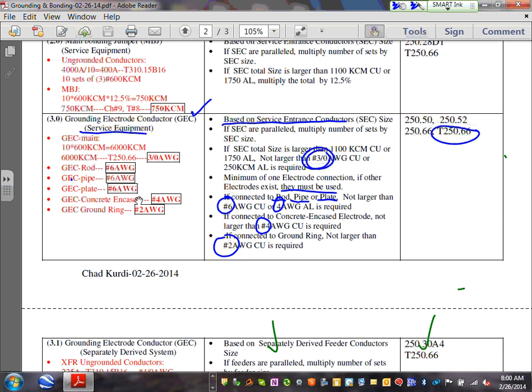When you have a grounding electrode conductor, you tie it to that copper plate, and then from that copper plate, you can go to a ring. Here's a rod. If you go to a rod, you don't have to go more than number 6 AWG. If you tie to concrete encased electrodes, a foundation, you don't have to go larger than number 4. If you tie it to a ring, a ground ring around the building, you don't have to go larger than number 2. Any comments? Any questions, gentlemen?